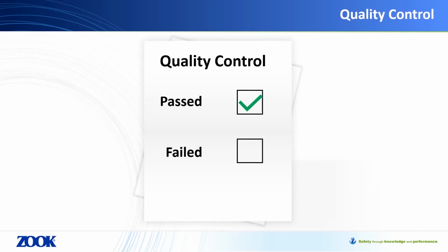Quality control is a critical component of the design and manufacture of rupture discs, holders, and welded solutions. Through stringent manufacturing standards and practices, your rupture disc manufacturer will ensure the performance of every single device shipped to your facility. In addition to the standard quality requirements, welded solutions may also demand additional testing to ensure expected performance. One of the challenges that must be overcome is performing validation of burst pressure and product performance on a single-use device. In order to ensure that product performance meets all customer requirements, a variety of both destructive and non-destructive techniques are utilized. We will cover this in two parts: destructive and non-destructive testing.